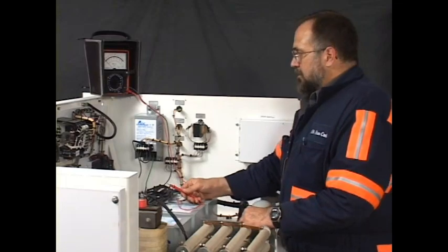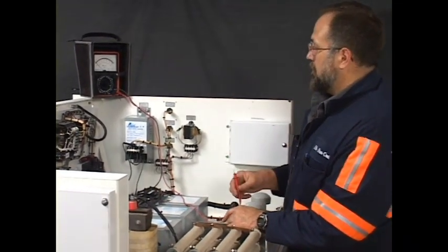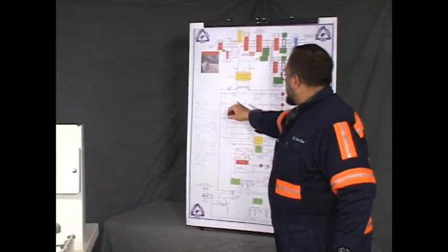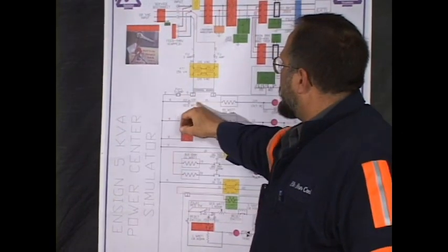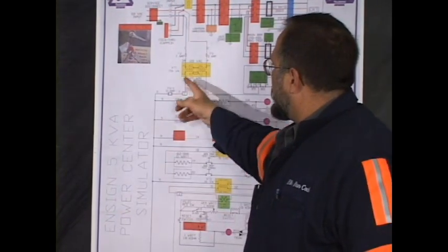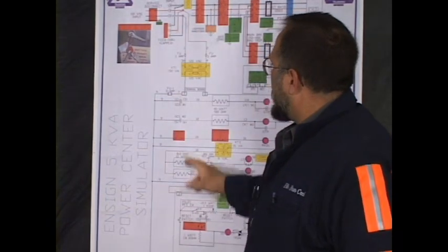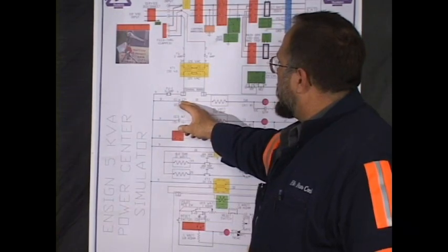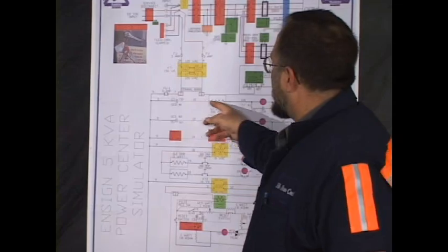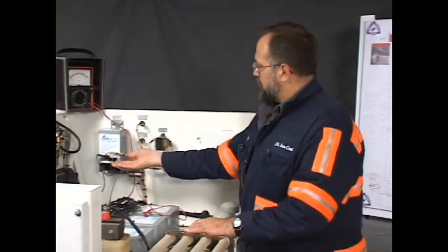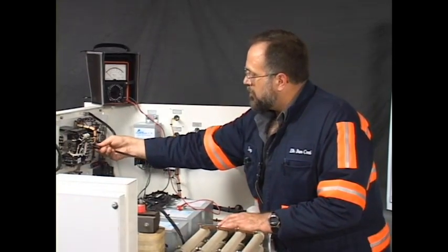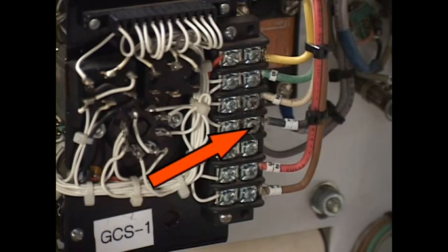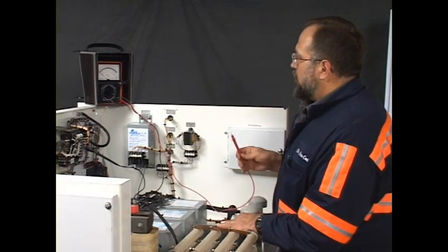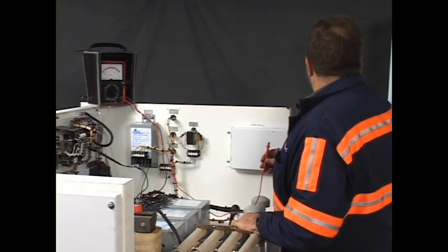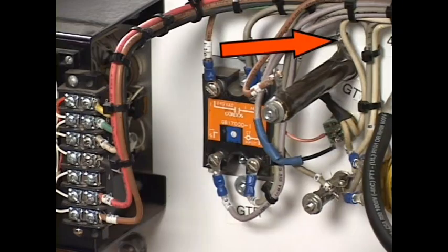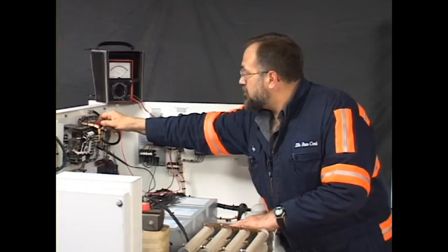The problem stated that GCS1 was closed. The contacts for GCS1 that close, wires 9 and 10, go to terminals 1 and 3 on the unit. We've completed a continuity test up to here. So now I'm going to move my black probe and attach it to terminal 3 for wire 10 and continue to follow the circuit out. The next point that can be read is on the end of the 40 watt 500 ohm resistor. On this particular unit, that's the wire in the back. And it's good. We have continuity.